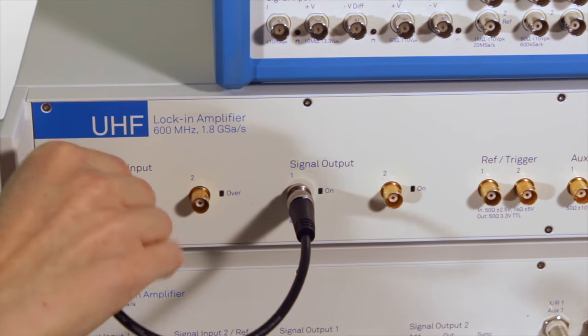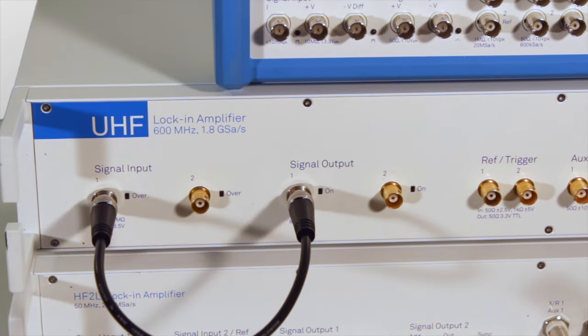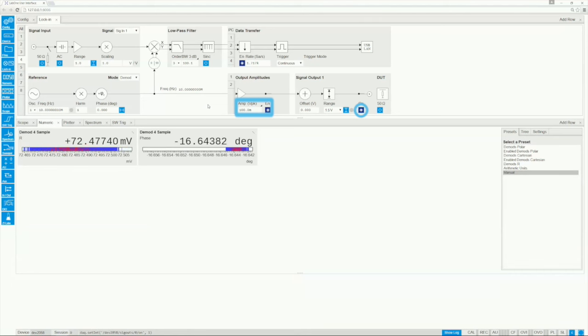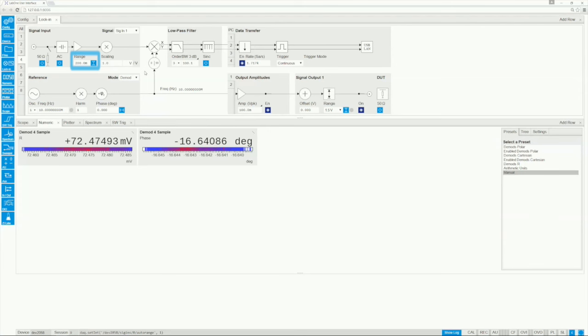In order to observe a signal we connect the lock-in output to the input and turn on the output with the default peak amplitude of 100 mV. On the input side we click the Auto Range button to adjust the input gain to match the signal to the range of the input digitizer.